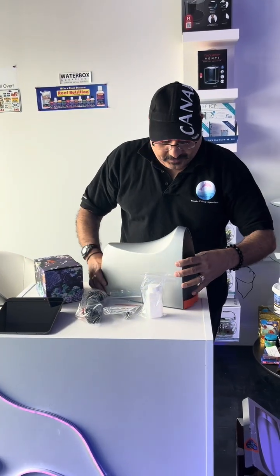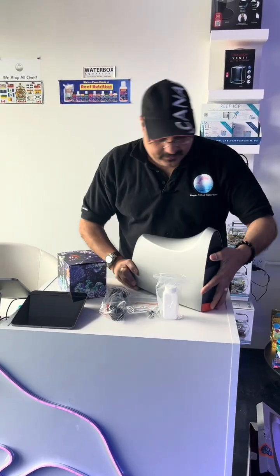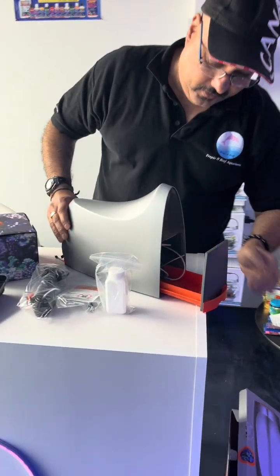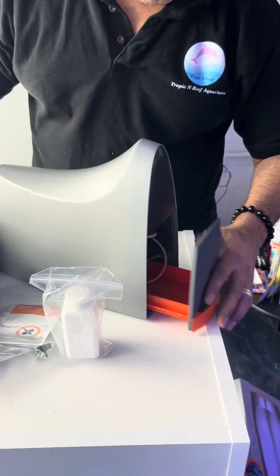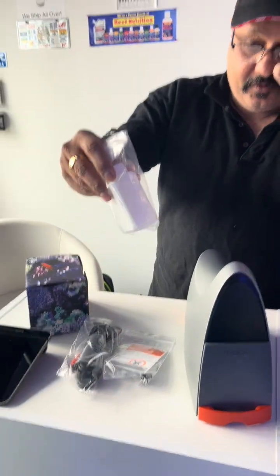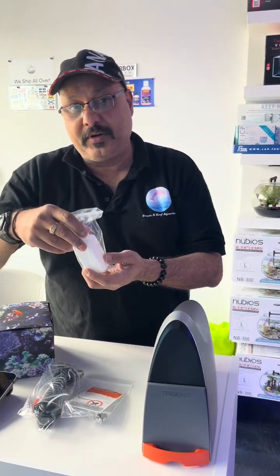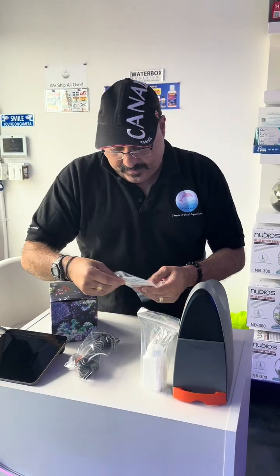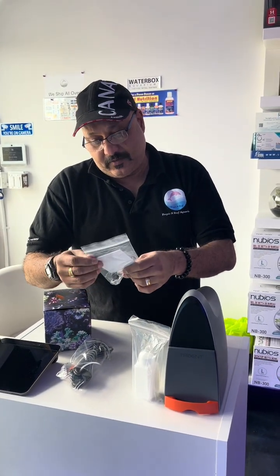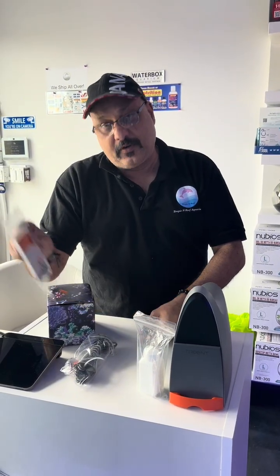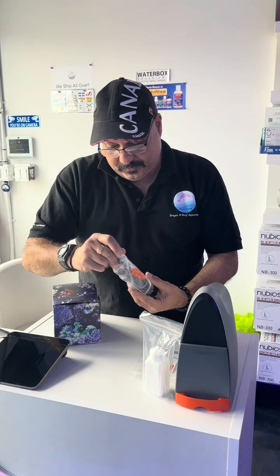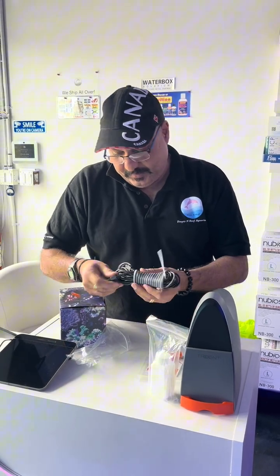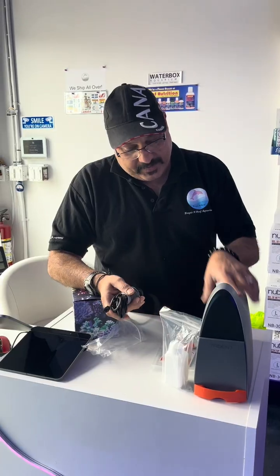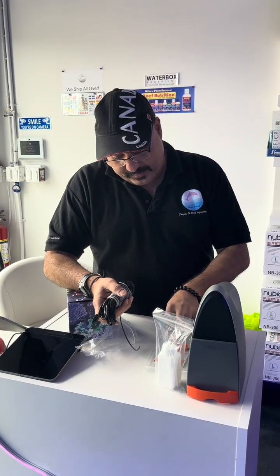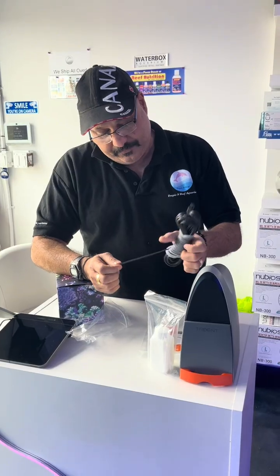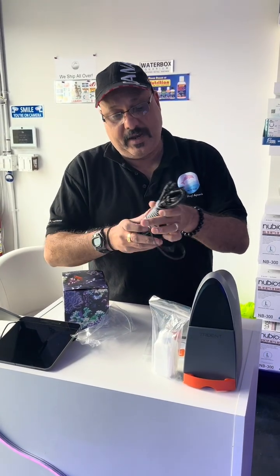So this is pretty much what you get right out of the box. This is the main unit, and you slide it out where you put all your three reagents: calcium, alkalinity, magnesium. This is the calibration fluid that comes with the unit. Very important, you've got to get this calibrated. And we have the spindle, which basically is required for your sampling of your line water. You have the hoses out here. One is your bus cable that's going to be connecting to your Apex to power this unit and configure it. And you have the intake and wastewater line given out here.